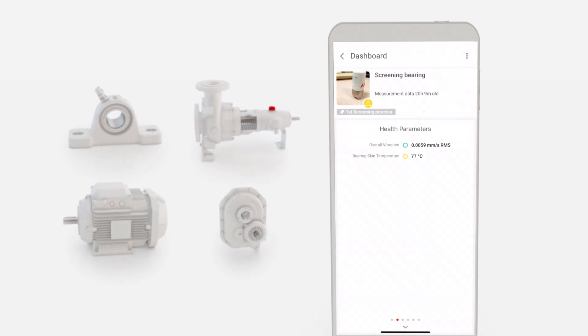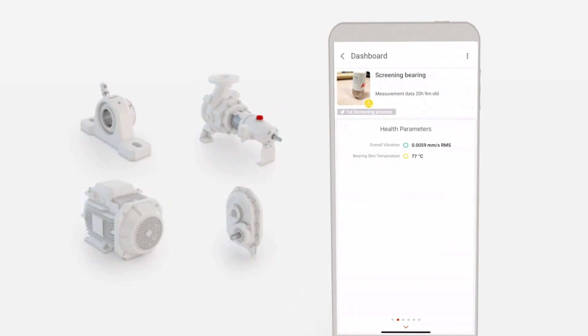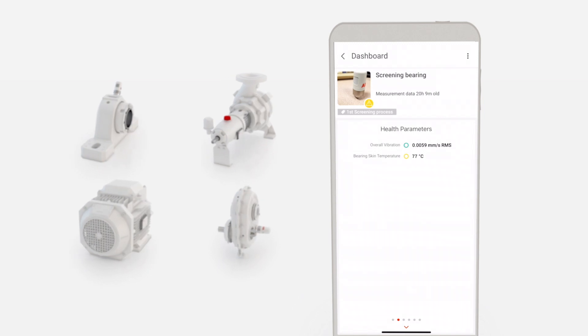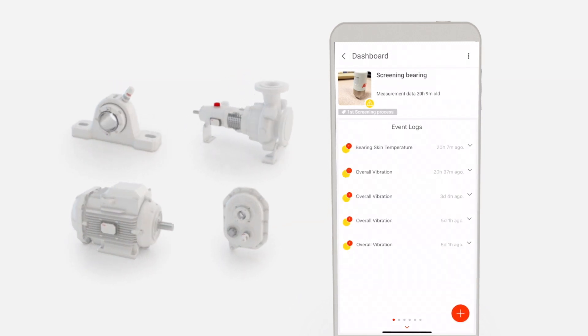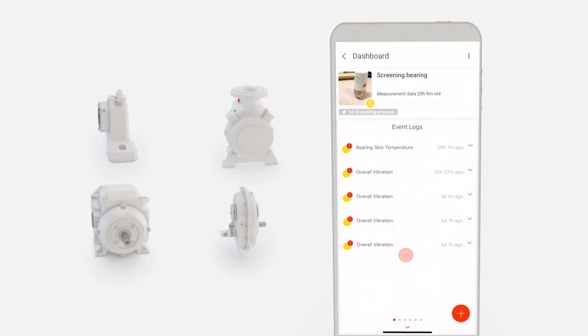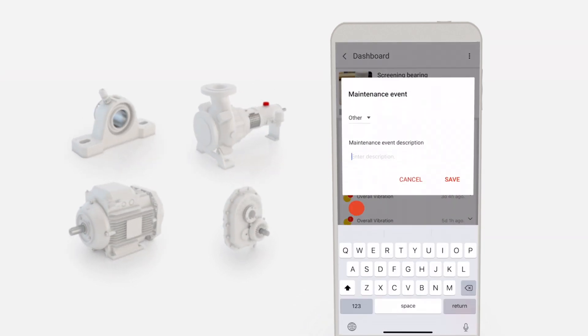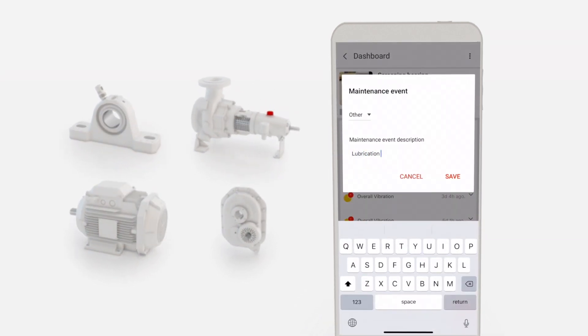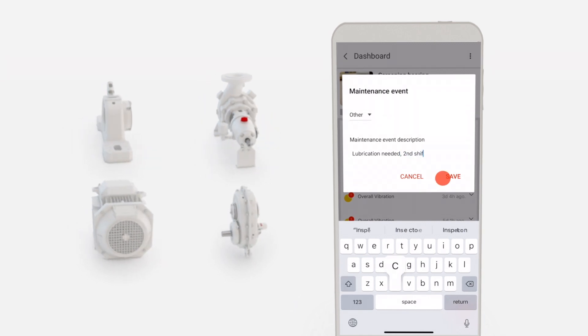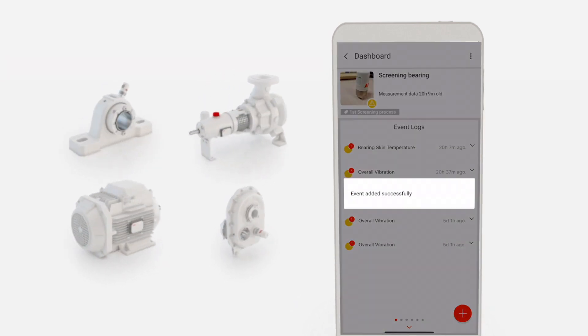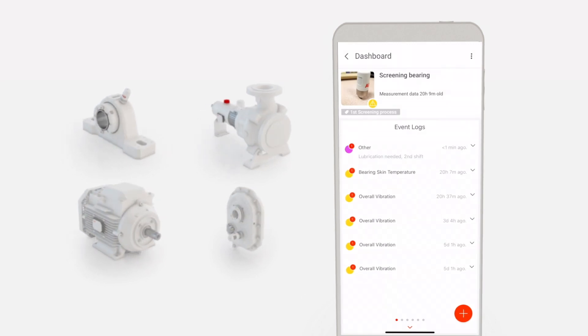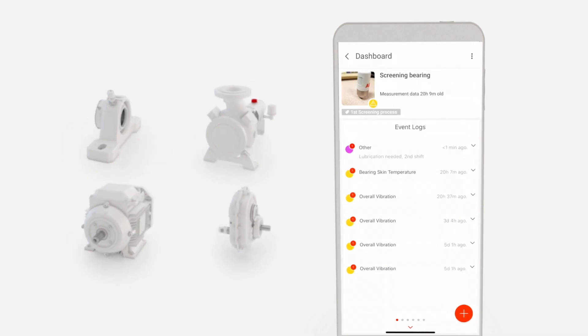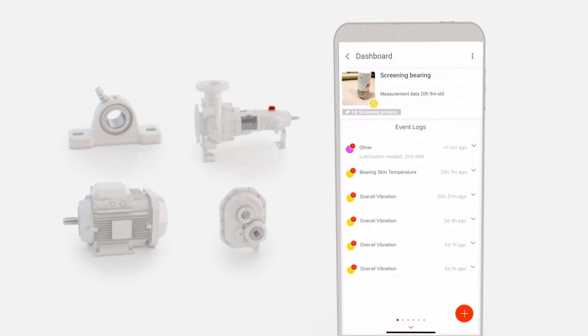Typically, a high temperature means the asset needs attention. A maintenance event can be created by clicking the plus symbol on the event log page for that asset. We'll type Lubrication Needed, Second Shift, and tap Save. This maintenance event will display across your organization within the ABB Ability platform for other users to see and respond.